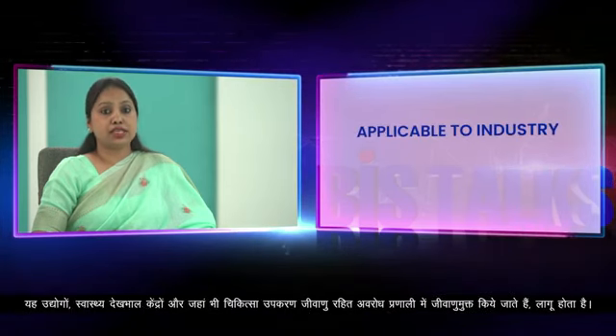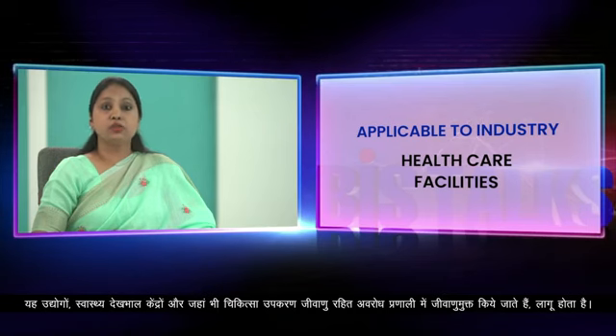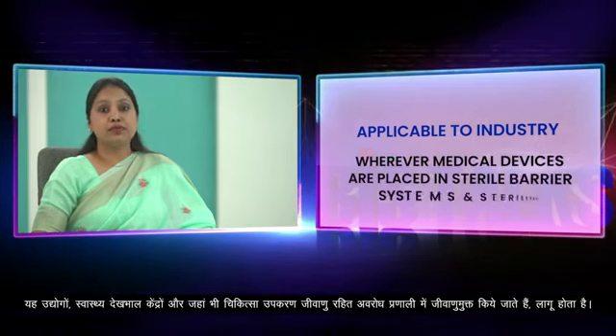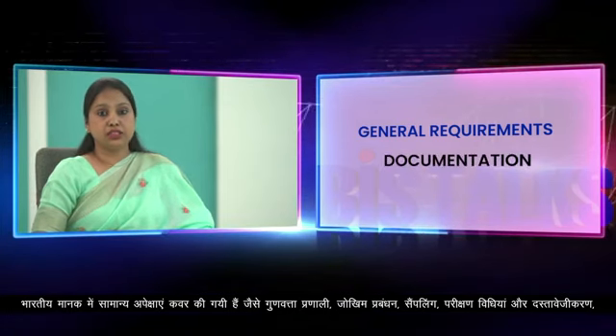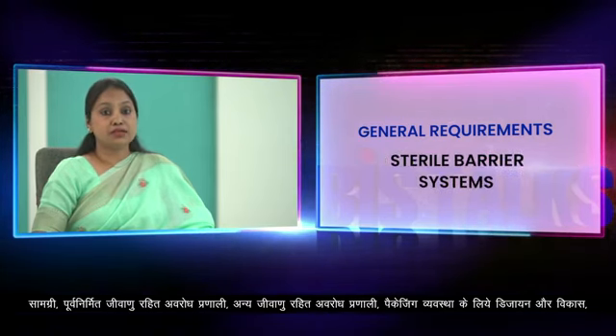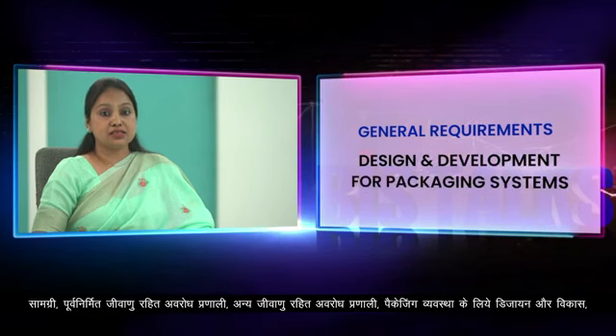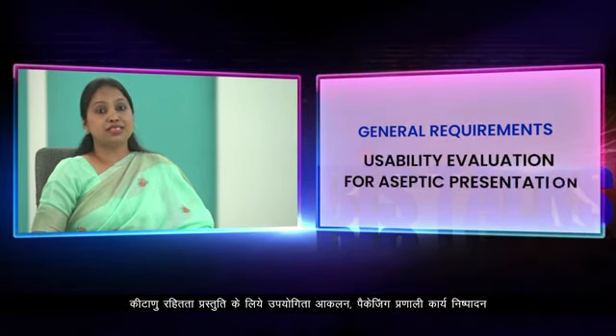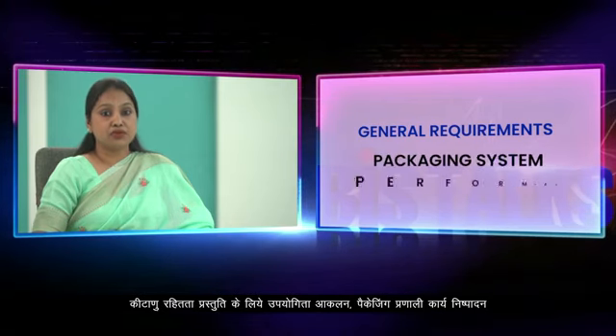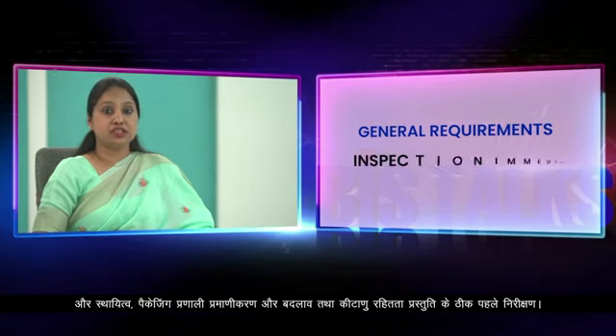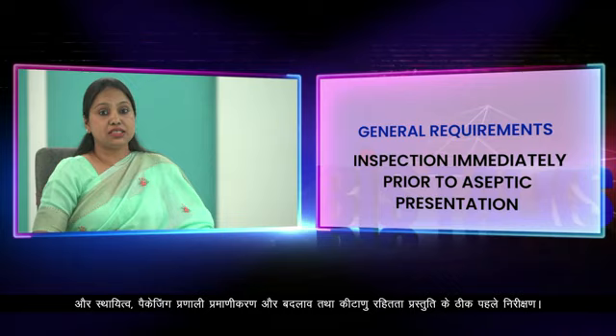It is applicable to industry, to healthcare facilities, and to wherever medical devices are placed in sterile barrier systems and sterilized. This Indian standard covers general requirements like quality systems, risk management, sampling, test methods, and documentation. Materials, preformed sterile barrier systems and sterile barrier systems. Design and development for packaging systems, usability, evaluation for aseptic presentation, packaging system performance and stability, packaging system validation and changes and inspection immediately prior to aseptic presentation.